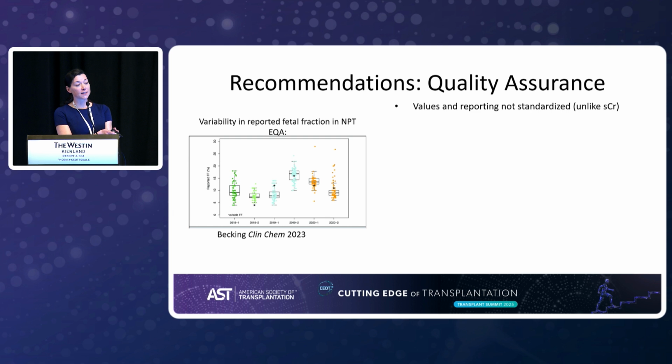So we feel that this is a really important point to think about for our field, because unlike serum creatinine, which is standardized nationally such that the value that one lab gets is translatable to the value another lab gets, there is no standardization of these assays across laboratories at this time. So we need to develop external quality assurance or proficiency testing programs.